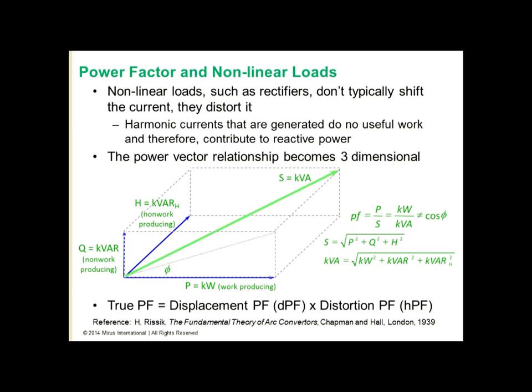Power factor is still real power over apparent power, or kilowatts over kVA, but it no longer equals cos theta. Cos theta is still referred to as displacement power factor. Apparent power, S, equals the square root of real power squared plus the inductive or capacitive component, Q squared, plus the distortion component squared. Or kVA equals the square root of kilowatts squared plus kVAR squared, inductive or capacitive, plus kVAR squared in distortion. So true power factor now is equal to displacement power factor, dPF, times the distortion power factor, HPF. And this is not a new discovery. The reference shown here at the bottom of the slide is actually taken from a text that was published in 1939.